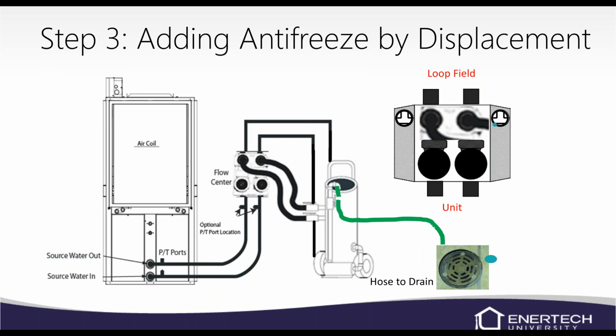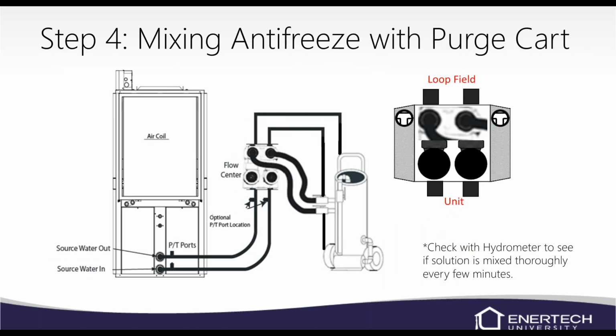After you get all your antifreeze in there, let it mix for a little bit, and then you're going to want to check your antifreeze level and see where you're at. Make sure you didn't add too much or not enough. Again, let it mix, let it flow through the system for a little bit, and then check with a hydrometer or a refractometer, or however you decide you want to check it.